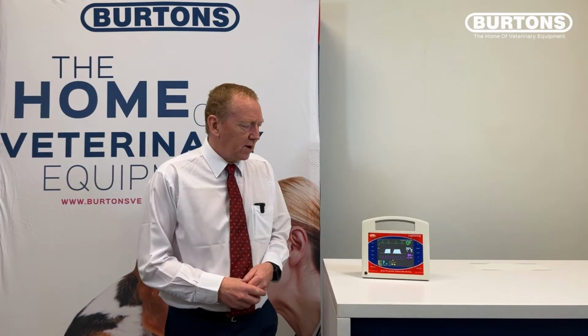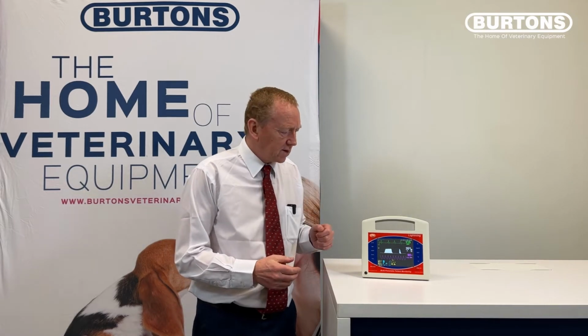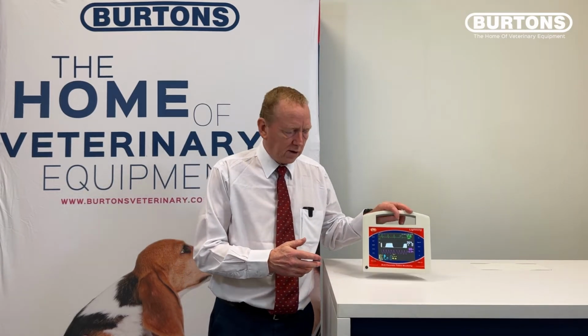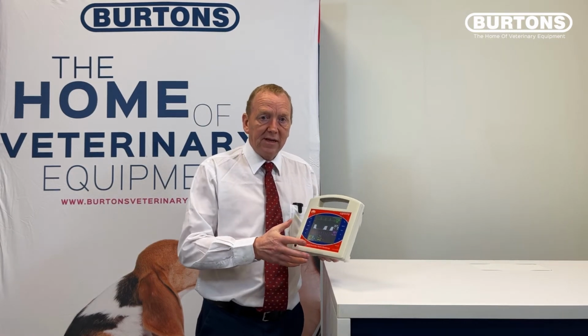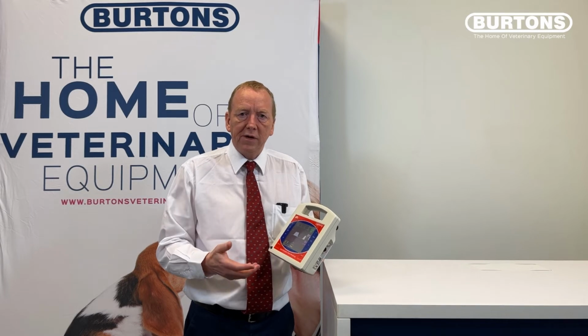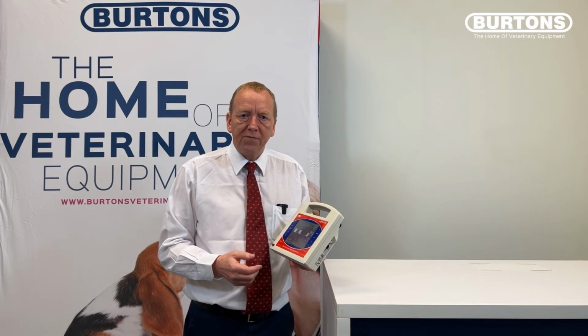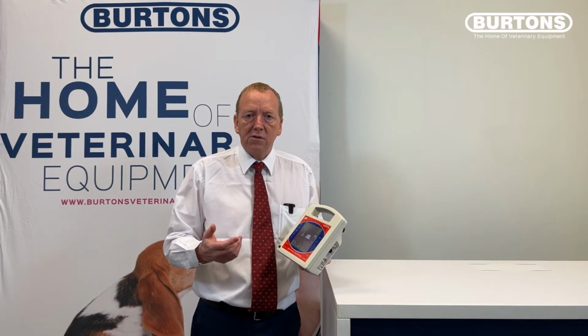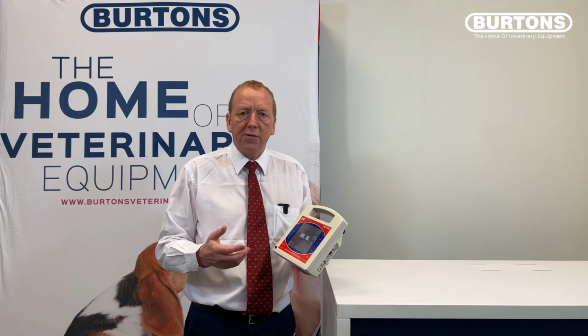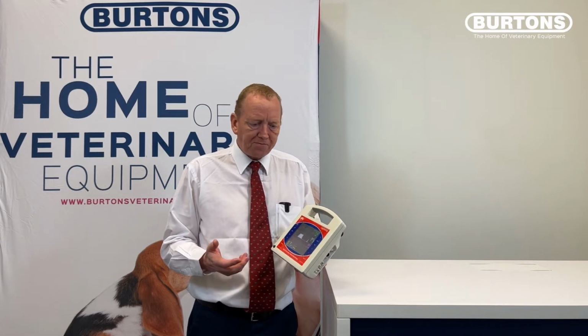So there are a couple of points I'd like to cover now. I've talked about modules for the unit and that different modules can be fitted. The nice thing about the unit is that it is entirely modular, so when you purchase a unit like this, you can decide to have just a CO2 module, a CO2 and ECG module, or any combination of all the modules available.